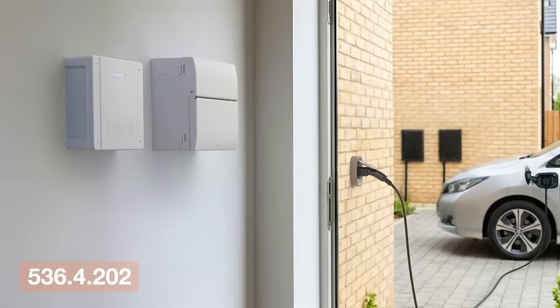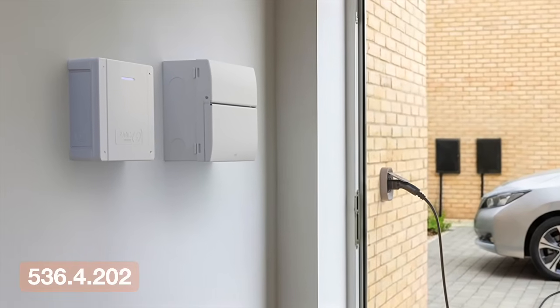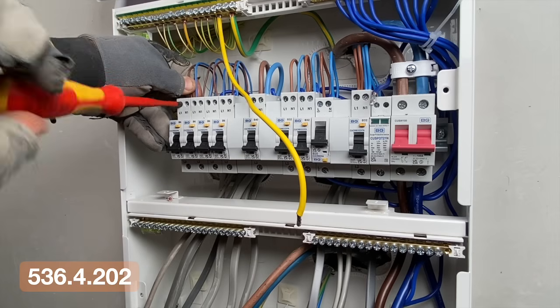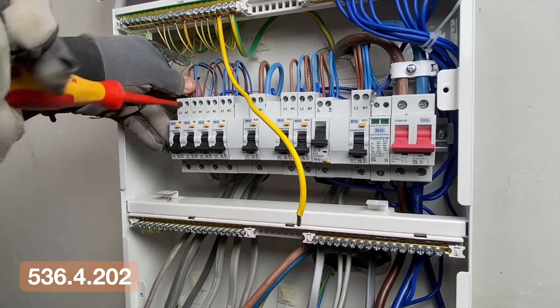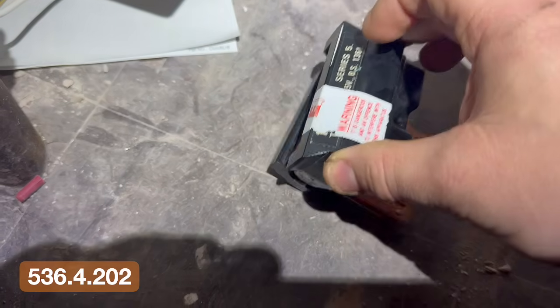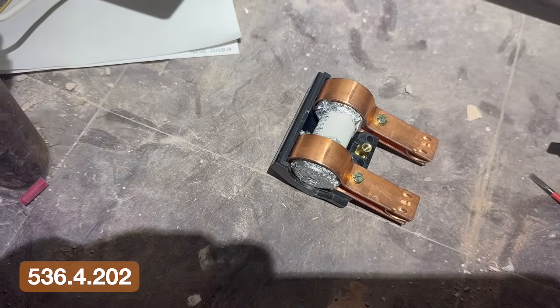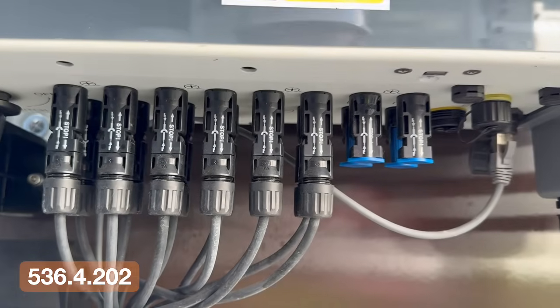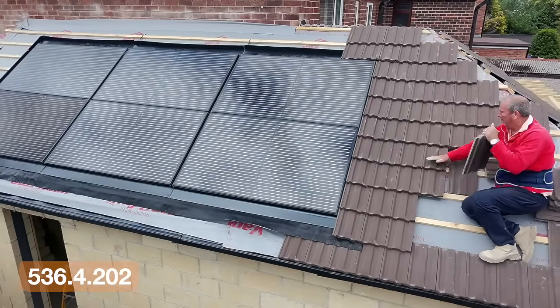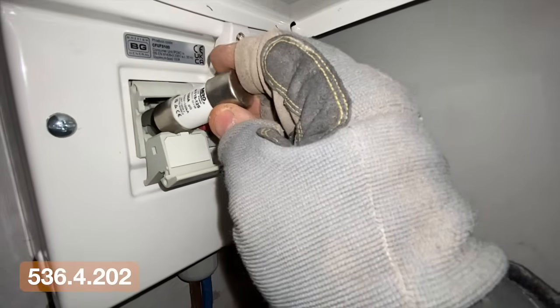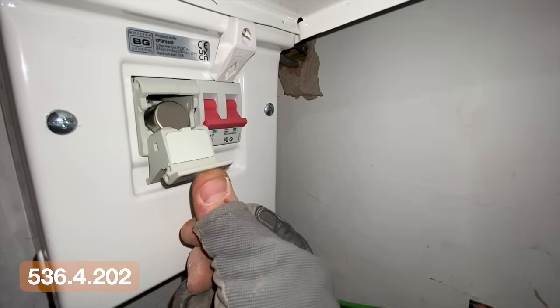So what does this mean? Well, the regulation is focused on making sure that the assembly itself is not overloaded. Traditionally, this was straightforward. You would select a protective device upstream that did not exceed the rating of the board. So if the board was rated at 100 amps, you would not protect it with anything higher than that. That still applies, but installations are no longer that simple. We now have multiple sources of supply, solar PV, batteries, EV charging, all interacting with the installation at the same time. The question is no longer just what is feeding the board, it is what the board could see in total. The regulation now gives you 3 ways to stay within the limits of that assembly.